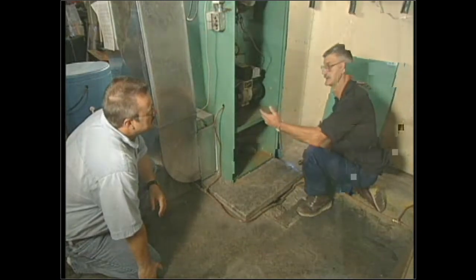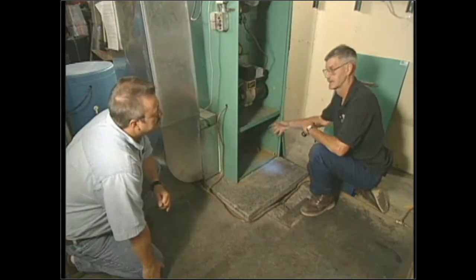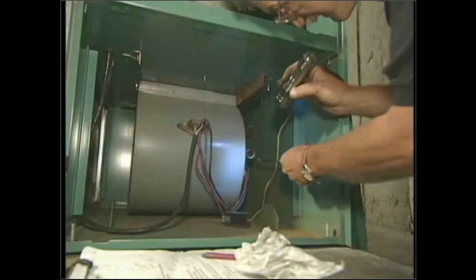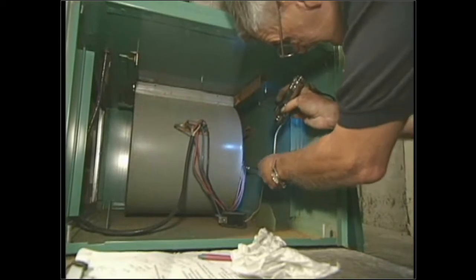I'll reach in and I'll feel the blower cage. The more that's built up, the less air that it moves. So we'll make sure that that gets cleaned. I'll do the same thing with this motor as I did with this one. I'll visually inspect to see if it is an oilable type or it has the sealed bearings. If it's oilable, I'll document that it needs to be oiled.